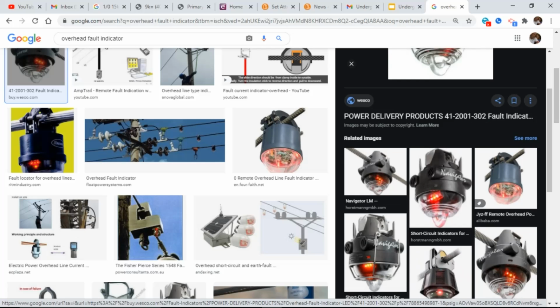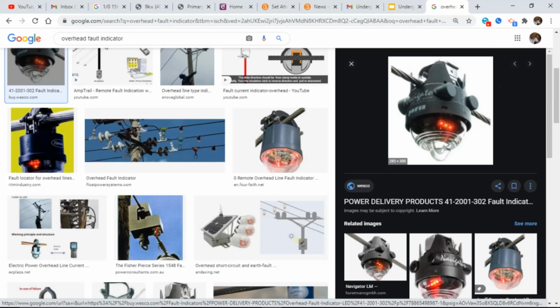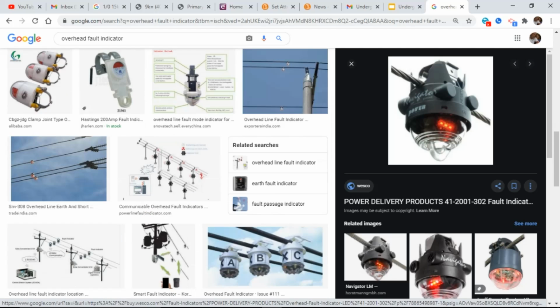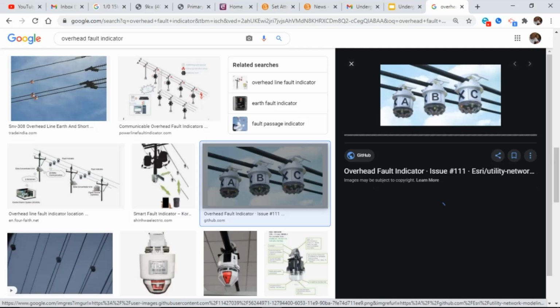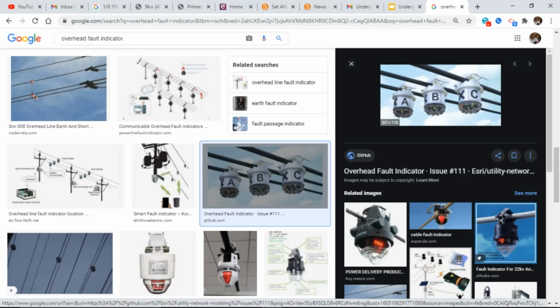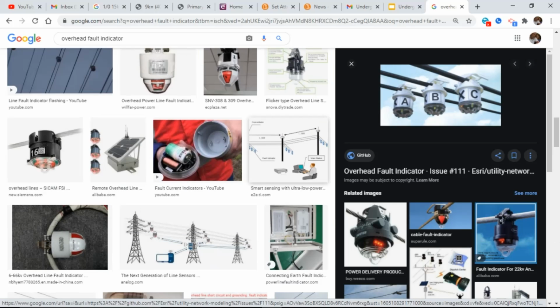Now, the technology has really, really grown on these things. Some of these things will actually tell you how many times the line has faulted. You see 3 red lights in there? It's faulted 3 times. Some of them will do 2. Some of them actually have radios in them. So a radio can contact SCADA via your dispatch center, and the dispatcher can call you. Yeah, we've got a fault indication at pole number 4, 5, 6, 7, 8, and you can just drive right to it. So the technology has come up a lot as far as fault indicators are concerned. Here you see some down here at the bottom. They actually put the phasing letters on them. So I did want to let you know they are in overhead also.